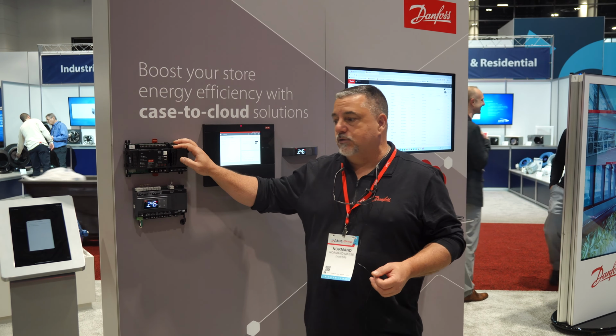In the system manager, we've really upgraded from our system manager 800 to the 800A. Beneath there is much faster quad core processing, just due to the amount of data that we're ingesting from all of the controls, so we've sped it up a lot. It's also touchscreen now, so we've gotten rid of the keyboard. We've also brought it into the next gen with some new protocols using RS485 and Modbus. There's a lot of features. It also has Wi-Fi connection for the technicians in the field that want to connect to it and not have to stand directly in front of it.